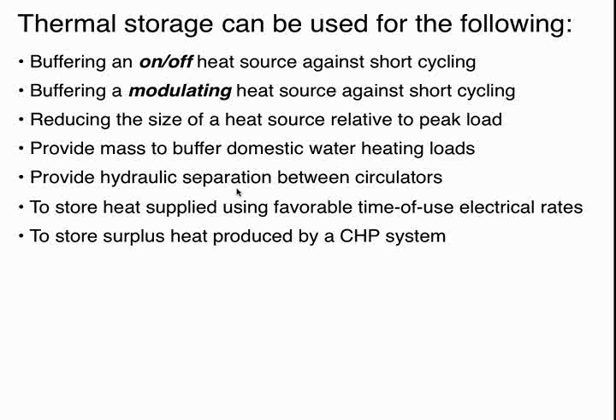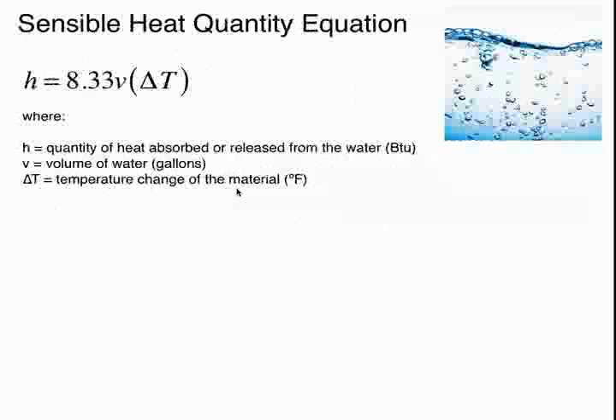If you're working with combined heat and power systems, again, thermal storage is a critical part of these systems. They tend to work best when the generator is running flat out hour after hour. And oftentimes we don't have a thermal load that can accept the heat of rejection of that generator set at the same rate that that heat is being produced. So we need to park that heat in storage.